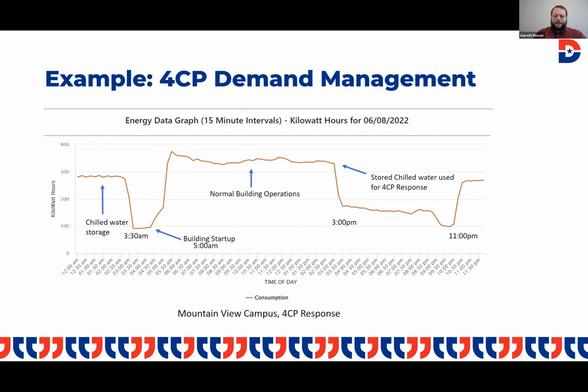This is an example of our Mountain View campus, which utilizes chilled water storage, a great asset for 4CP demand management. At every location, when we send out a 4CP alert, every campus takes action to reduce load during those times, but it's much more pronounced with chilled water storage. The system isn't sized to carry the load the full day, but we can use it very effectively during the 4CP period and through the end of the occupied day.